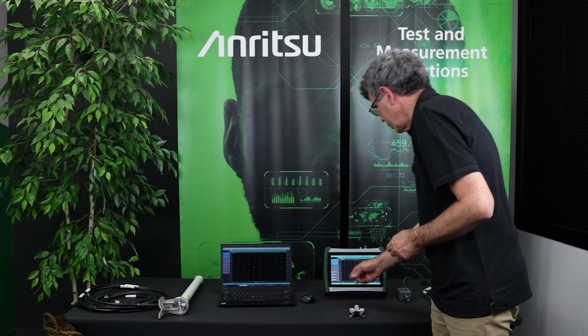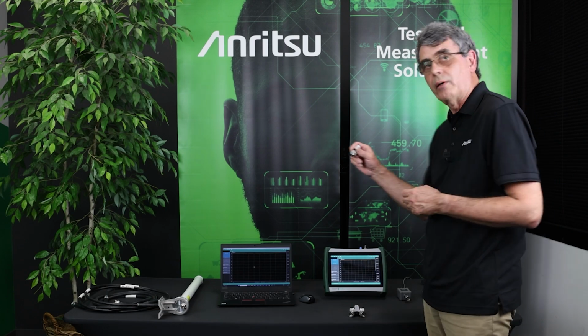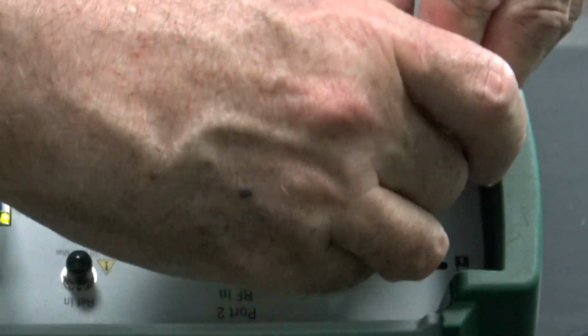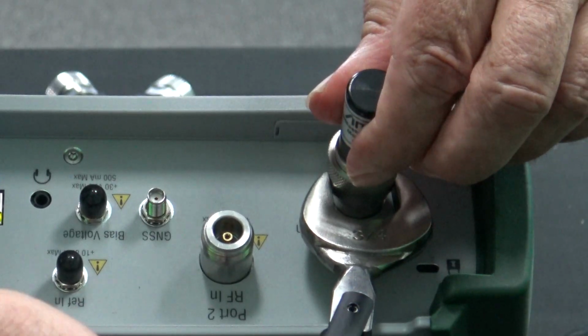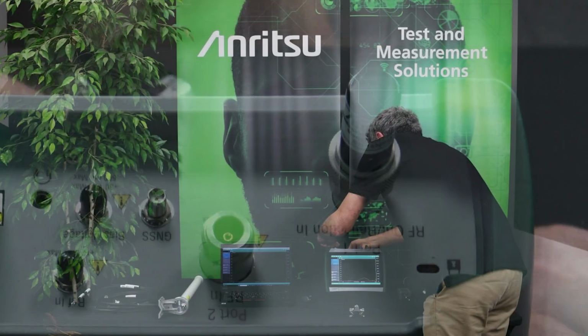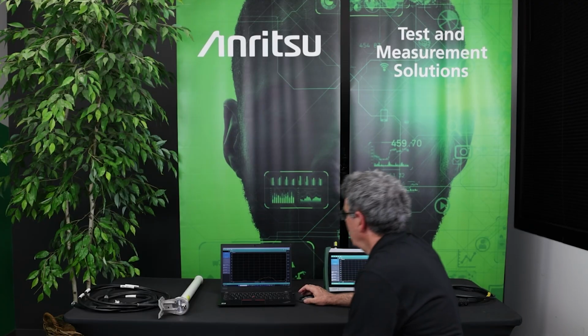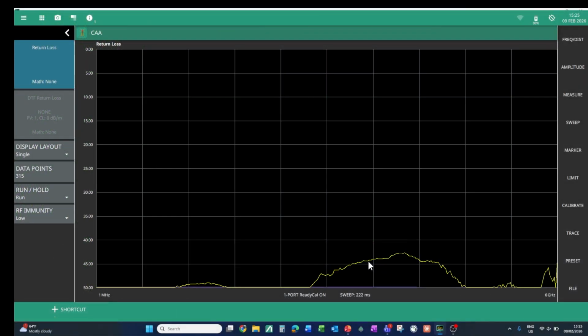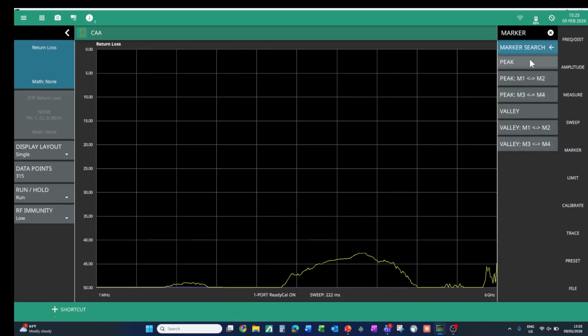So let's just have a look. We're sweeping here from roughly DC to 6 gigahertz, and I've got a precision load. So I'm going to put the precision load onto the test port. I've got the ReadyCal data being applied. It's applied by default when we turn the instrument on. And having connected up the load and just using a torque wrench to tighten that up nicely, we can see here on the screen that we're getting better than 40 dB return loss on this. If I go into the marker menu and do a marker peak search, the highest reflection there is at about 42.7 dB. So the ReadyCal at room temperature at the test port does give us a very good directivity, a very good ability to measure return loss.